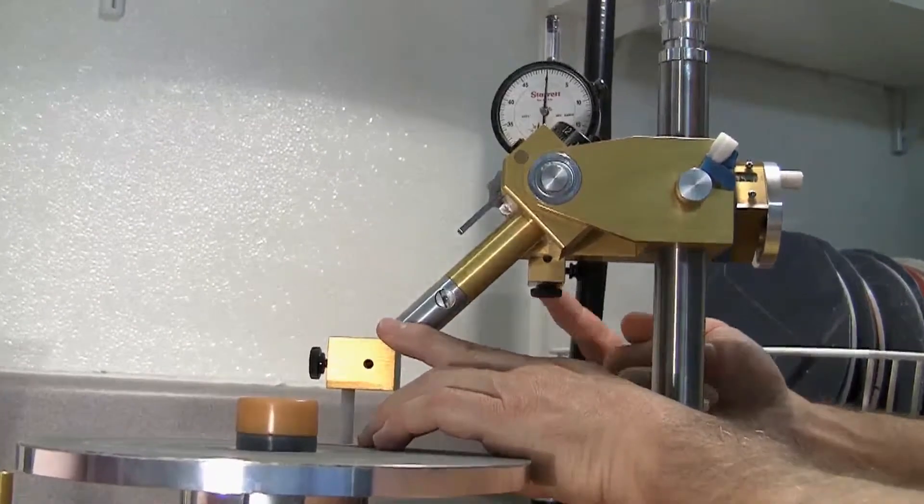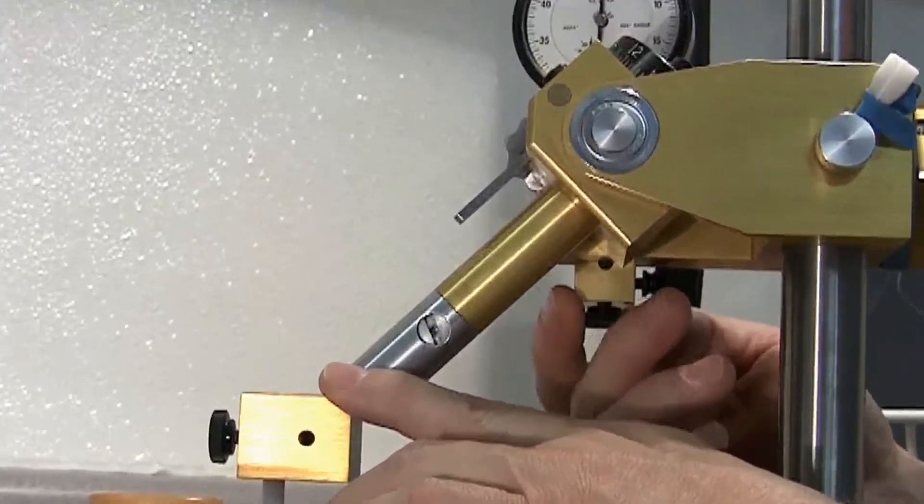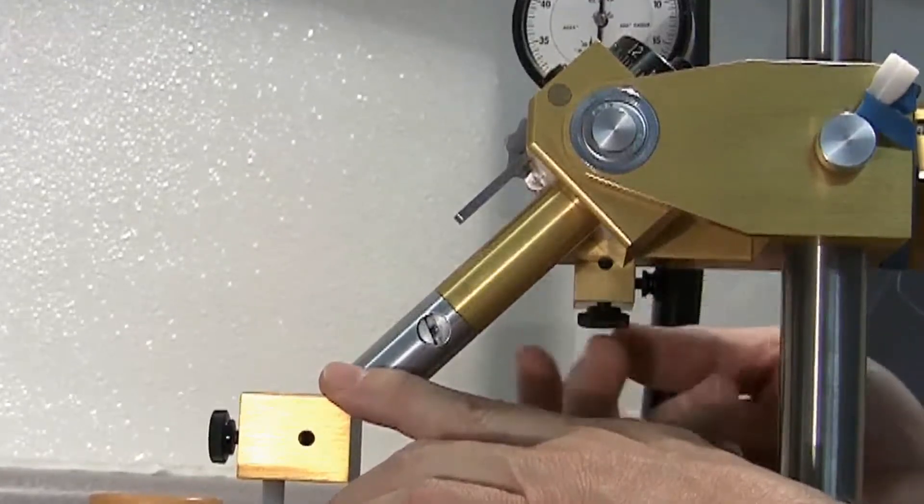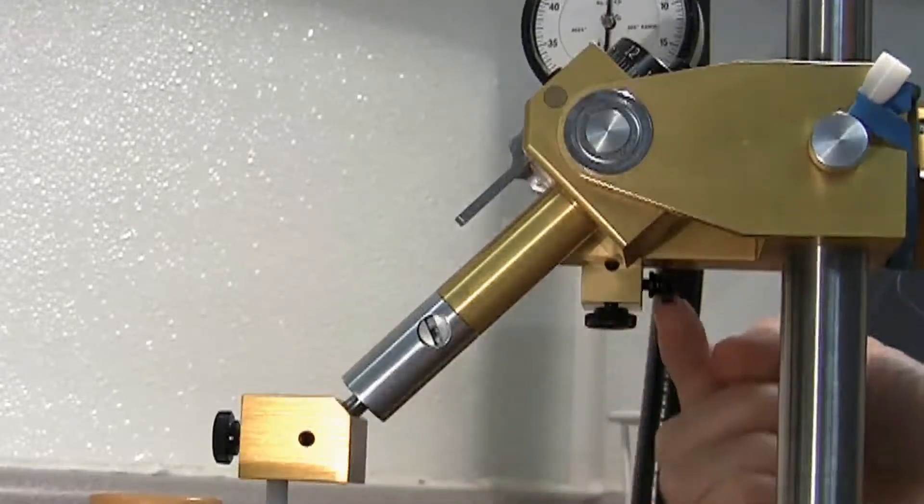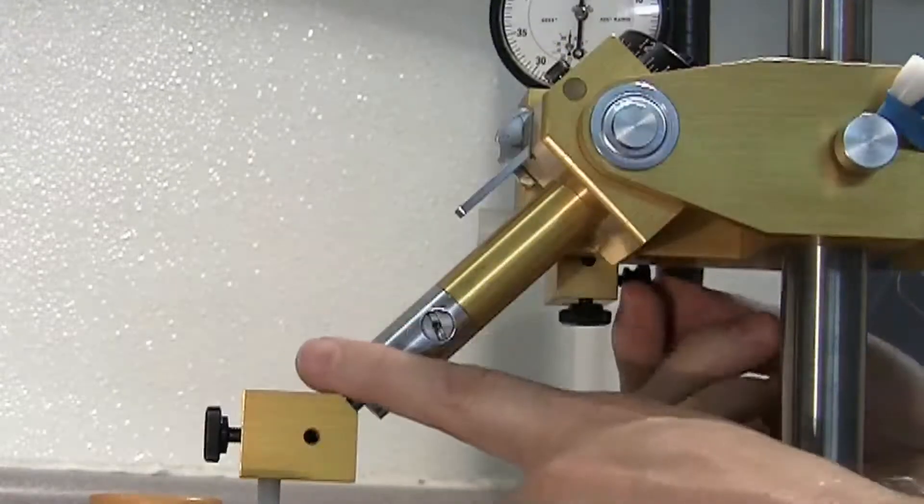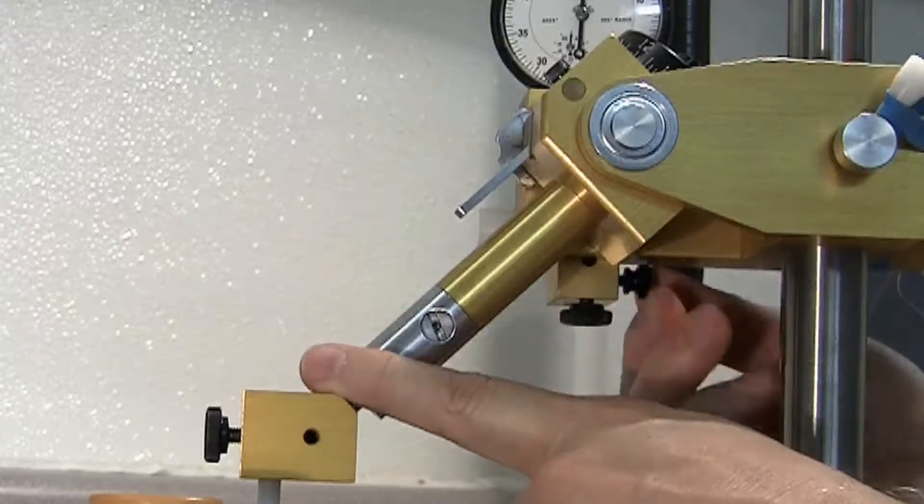We don't want the hard stop control knob creeping in or out. We don't want this to change while we're working on the machine. So if this knob is loose, we just add a little bit of tension. That's all this other thumb screw is for right here, is to add a little tension so the actual adjustment doesn't creep around.